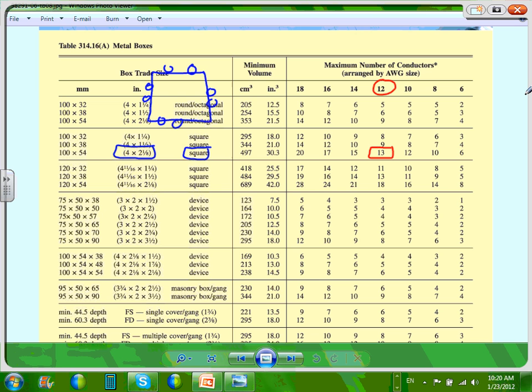So if I want to go with 12 conductors, 1, 2, 3, we have 8, 2 times 4, 8. 8 times 2, 16. I have just exceeded how many conductors I can fit in this box. Can you guys see that? That's why, if you have a fixture, it's a good idea: you bring one here, and one here, and one here, and one here. Suppose the fixture has a number 12, so this is 2 number 12. So 1, 2, 3, 4 times 2, 8. I can bring 8, and I'm limited here to 12.